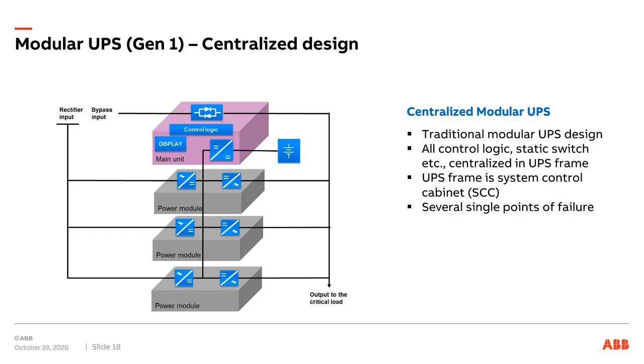So thinking back, this is kind of the reason why I went through the history of how we progressed through the development of paralleling monolithic UPSs. This is very similar. In this case, the UPS frame, the cabinet, is taking the role of the system control cabinet, and customers can slide in modules, like in this one, showing 3, but as I mentioned, I know there are products out there with space for up to 20 different modules. So it serves the purpose. Customers can add modules as they need them, and they can have built-in redundancy. Like in the same example as before, if 2 of the power modules here can feed the load, there's N+1 redundancy on the power module at least.